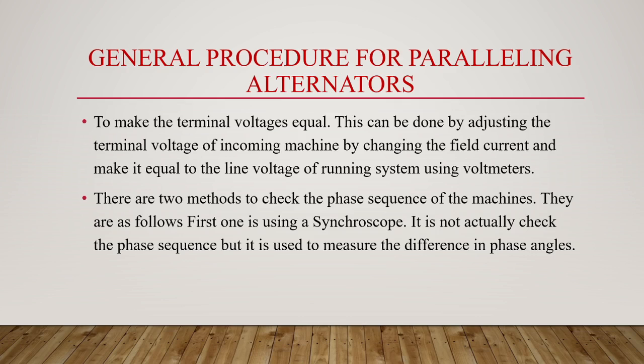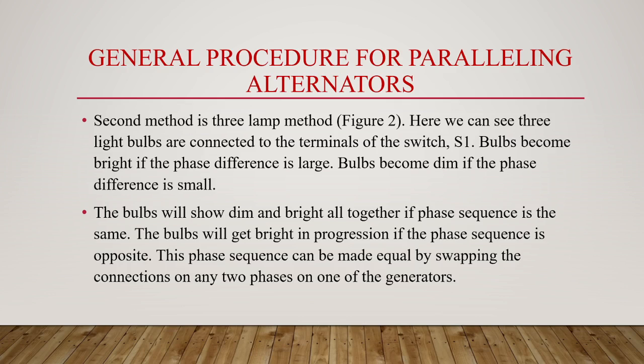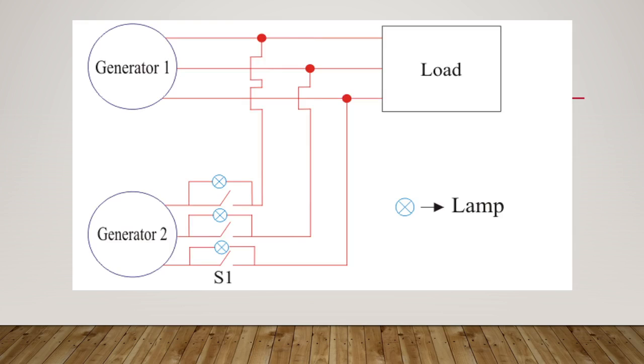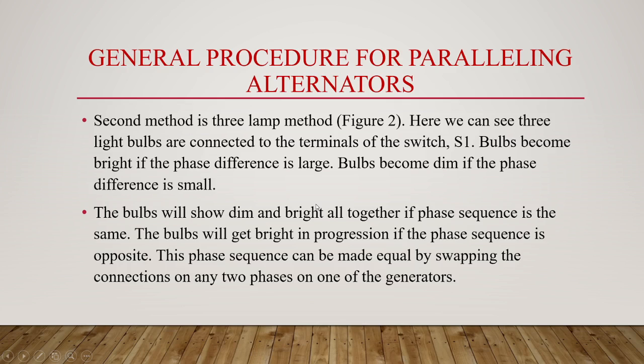So there are two methods to check the phase sequence of the machines. The first one is using a synchroscope. It is not actually checking the phase sequence, but it is used to measure the difference in phase angles. The second method is the three lamp method. We can see here three light bulbs are connected. One, two, three.